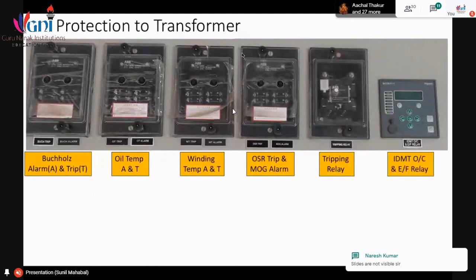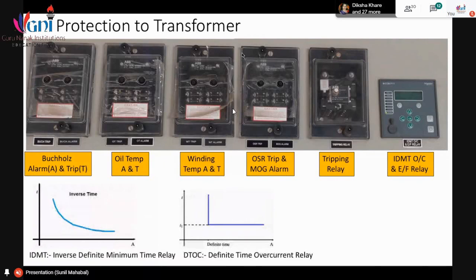Then there are the IDMT, overcurrent, and earth fault relays. This is for the distribution which is there in the plant. If any cable develops a fault, earth to neutral or phase to phase, then it can sense and trip. The full form of IDMT is inverse definite minimum time relay. The timing and the amperage sensed by that relay are inversely proportional. As the current passing through the relay increases, the time required to trip the circuit reduces. Therefore, it is inverse time.